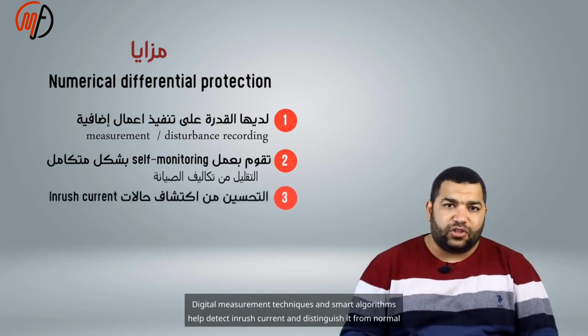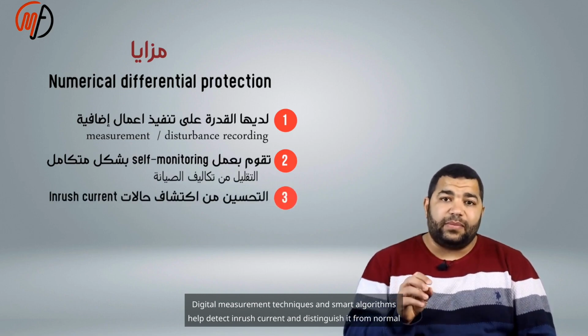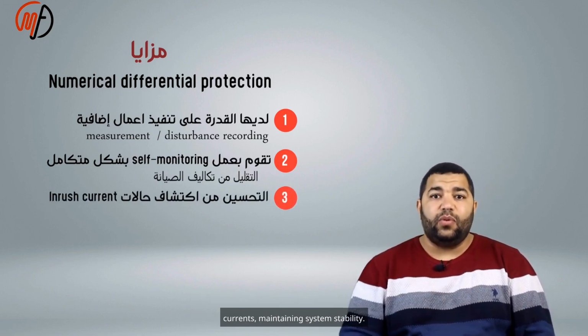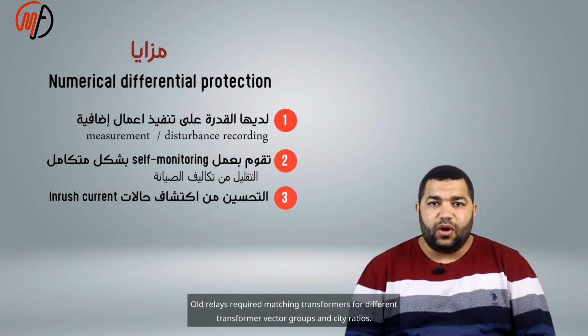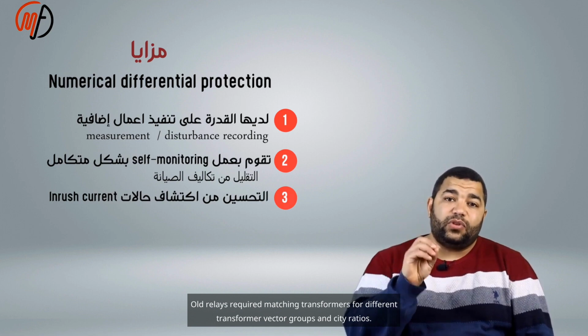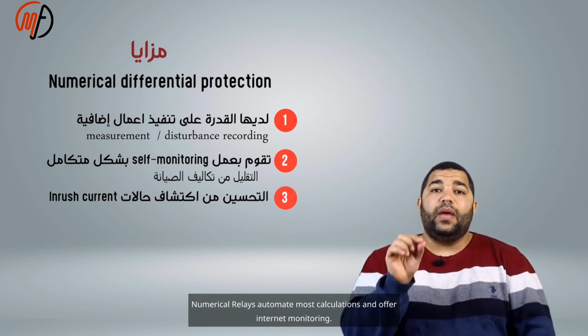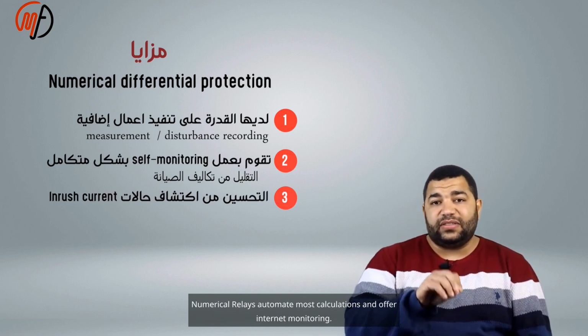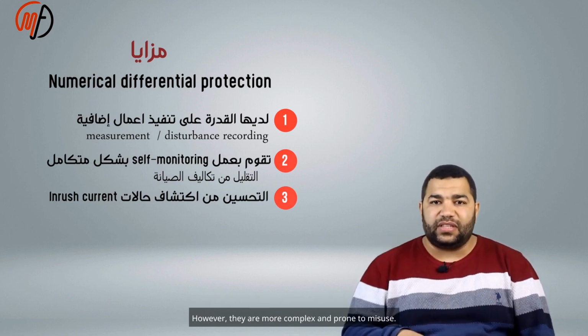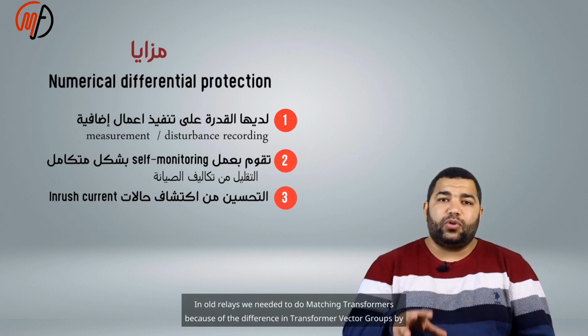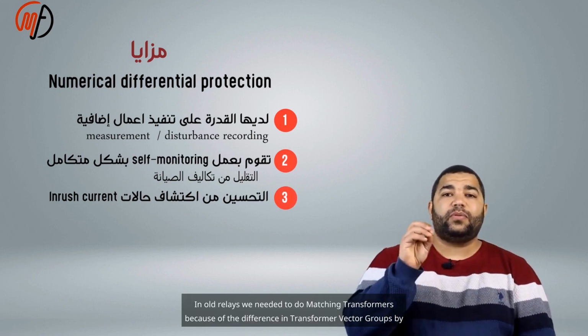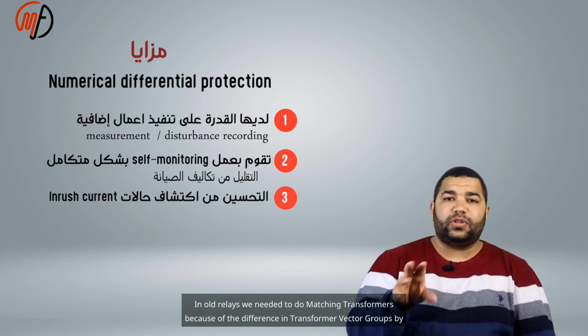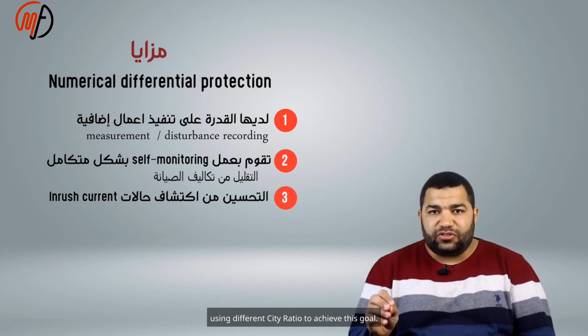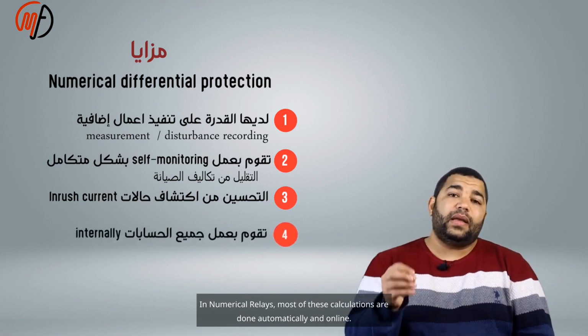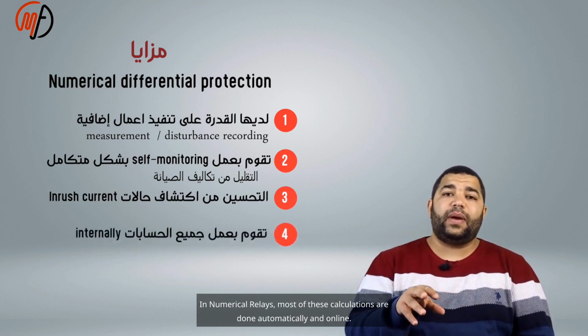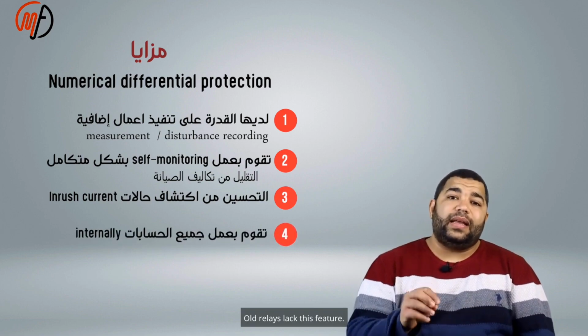Digital measurement techniques and smart algorithms help detect inrush current and distinguish it from normal currents, maintaining system stability. Old relays required matching transformers for different transformer vector groups and CT ratios. Numerical relays automate most calculations and offer internet monitoring. However, they are more complex and prone to misuse. In old relays, we needed to do matching transformers because of the difference in transformer vector groups by using different CT ratios to achieve this goal. In numerical relays, most of these calculations are done automatically and online. Old relays lack this feature.